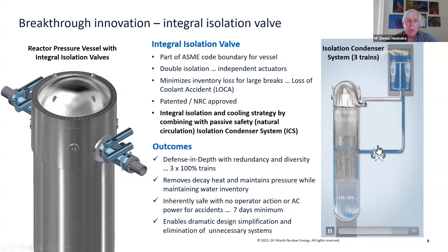So we were able to take what was the pinch point for the reliability for isolation condensers, which a lot of you have heard me talk about, software common cause. Driven by software common cause and digital I&C, which was about a 10 to the minus 4 failure rate. And now we're able to reduce that down to something on the order of 10 to the minus 7 failure rate for isolation condensers. So we have a much more reliable passive system here with the current isolation condenser system.